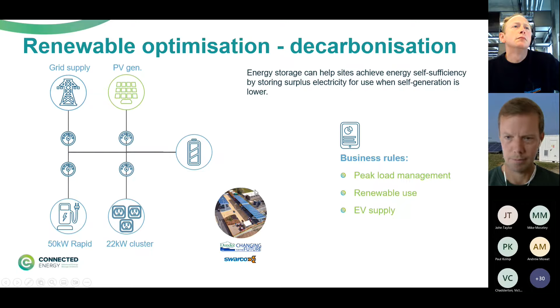So it's powering these 22 kilowatts and the rapid EV charger, which is then offsetting grid electricity. So we're not using grid electricity when the sun is shining, we're capturing the PV into our battery, and then we're putting it out into these EV chargers. And we can monitor this in real time. So this site went from 85% renewable optimization up to around about 99%.